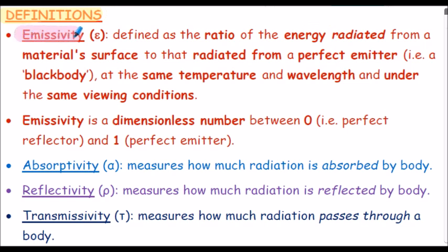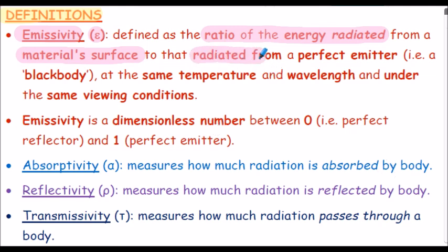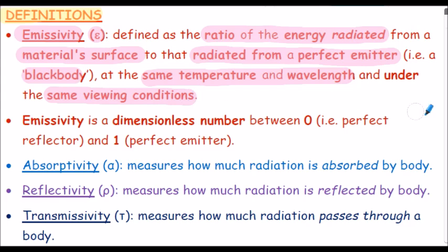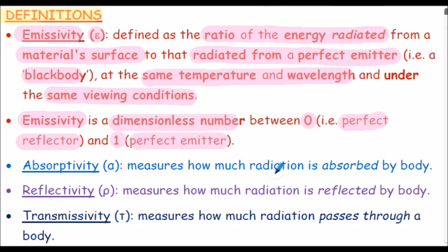Here are some definitions for your reference. Emissivity, symbol lowercase epsilon, is defined as the ratio of the energy radiated from a material surface — the body's surface — to that radiated from a perfect emitter, that's usually termed a black body, at the same temperature and wavelengths, under the same viewing conditions. Emissivity is a dimensionless number ranging between 0 for a perfect reflector and 1 for a perfect emitter.